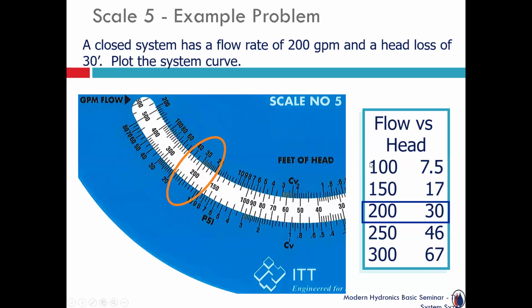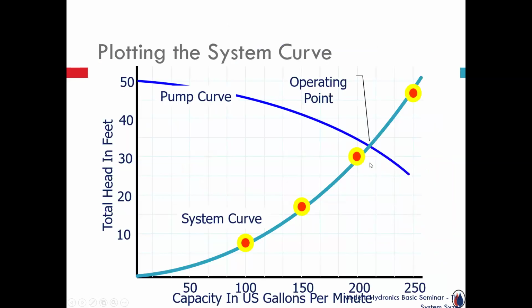300 gallons a minute, read straight up, 65, 60, 70, so about 67 feet. So then what would happen is, again, years ago, today, software does it for us automatically. It's all instantaneous. But you would plot a curve, and you'd put those numbers down and create the system curve. And where that curve intersects, ideally, is where you want that pump to be operating. That's the conditions you created, 200 at 30 feet of head.